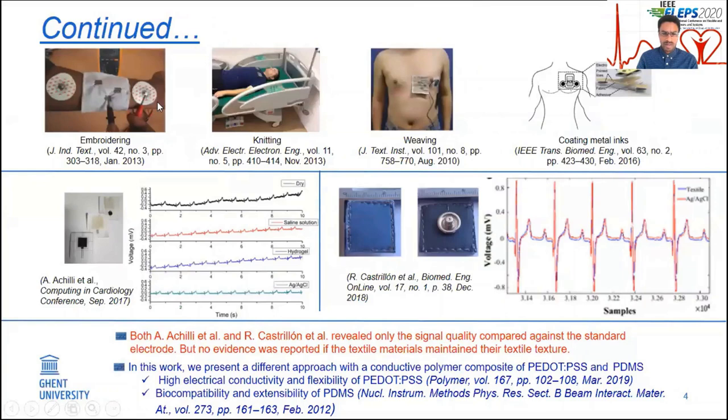To use a textile as an electrode, it must conduct electricity. This can be achieved by integrating conductive yarns or conductive filament fibers into the fabric structure via embroidering, knitting, weaving, or by applying metal inks, conductive polymers and their derivatives onto the textile substrate by coating, printing, plating, and other techniques. For instance, Achilli's and Castrillón's teams have developed a textile-based ECG electrode using PEDOT:PSS as a conductive track via screen printing. In both these works, the ECG signals collected by the textile-based ECG electrodes were strongly comparable with the standard electrode.